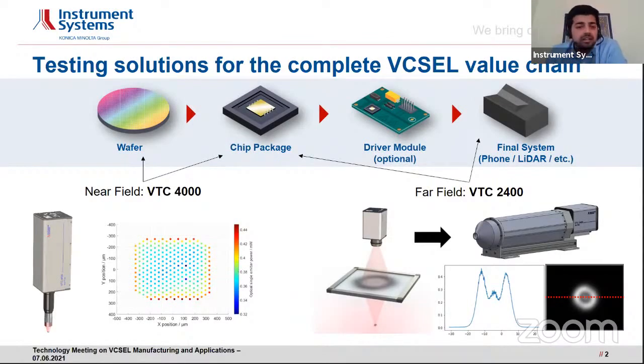The really great thing is that the camera is completely and absolutely calibrated and traceable to our national institute, which gives really unprecedented uncertainty budgets. Especially for the far field, which I'm coming to soon, when it comes to laser eye safety parameters or determining the laser class of the DUT, such traceable data is always an added advantage.